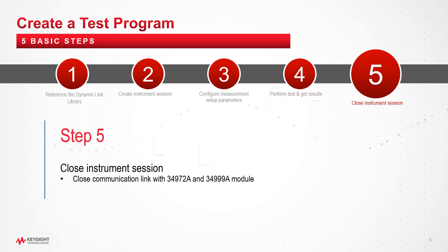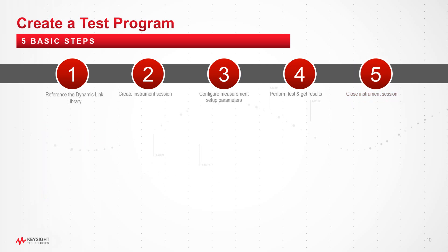At the final step, before ending or closing the program, it is always good practice to properly disconnect the communication link with the instrument and release the driver handle to free up the memory space used by the driver DLL.